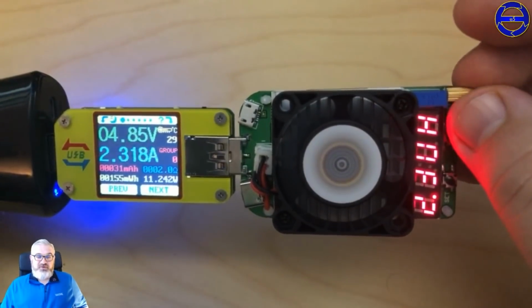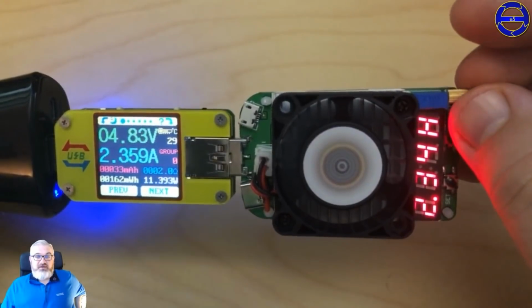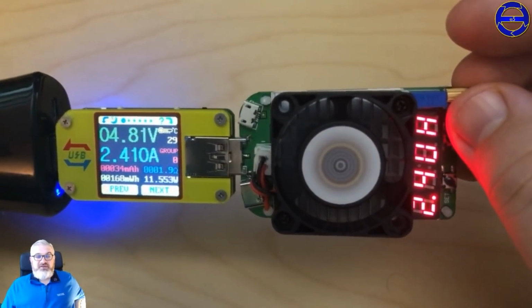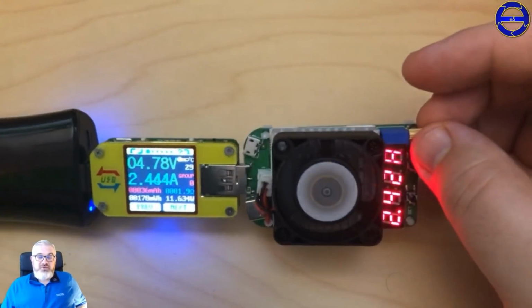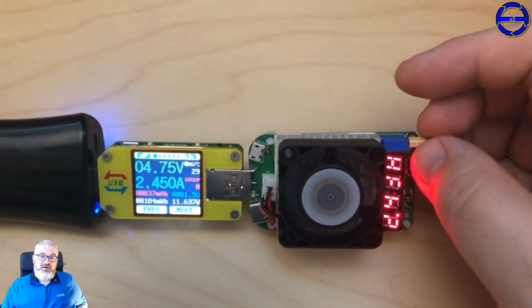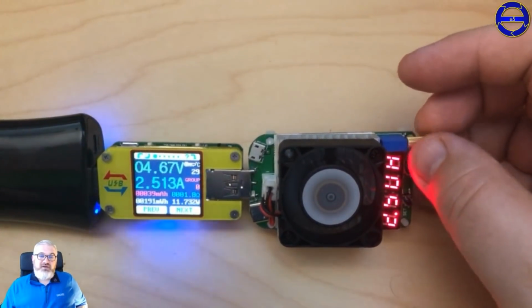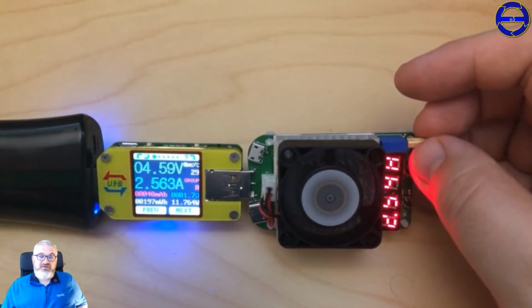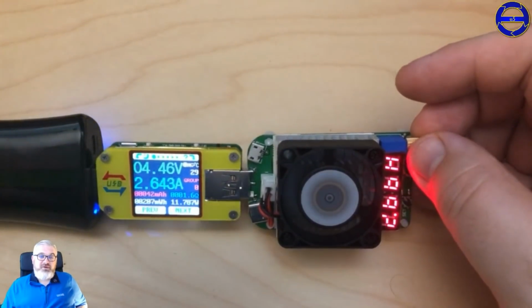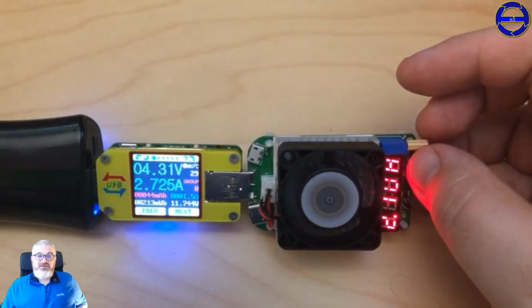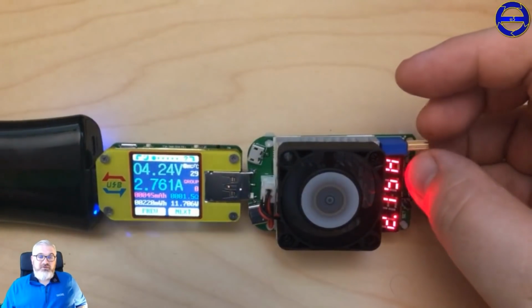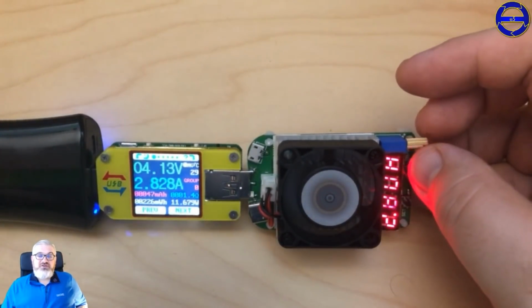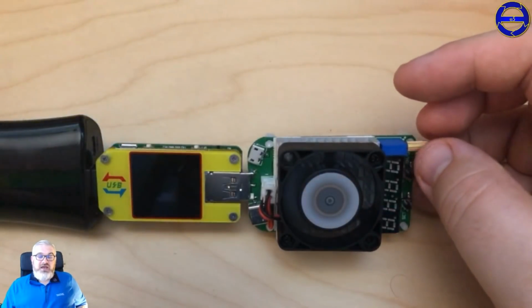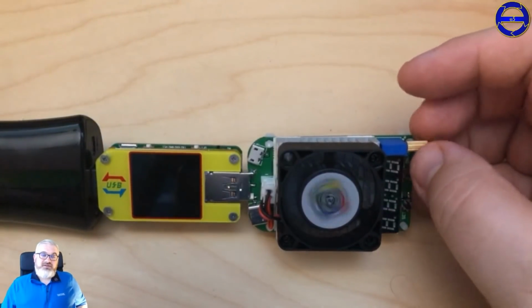So 2.2 amps, I'm still going. 2.3, so I'm going a bit above what the manufacturers have stated. 2.4 amps, so straight away I'm 0.3 of an amp above, and I'm now at 2.5 amps on a 2.1 output. 2.6, 2.7, so I'm wondering now if there's a protective device or not. 2.8, and of course it's tripped out. There we go. So the device itself has switched itself off to protect itself.